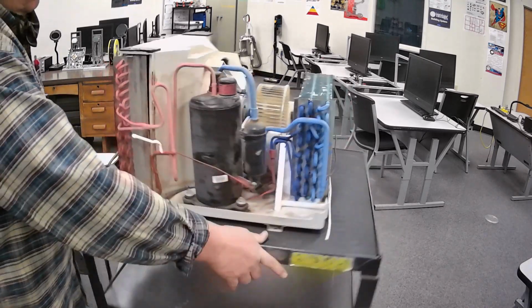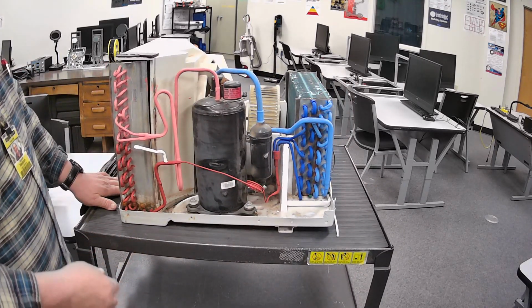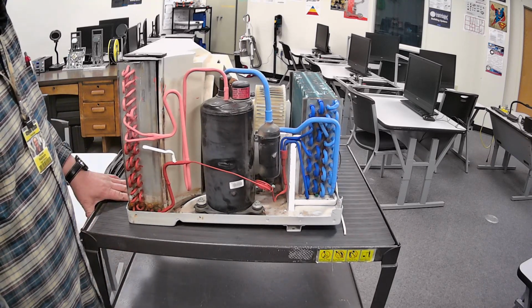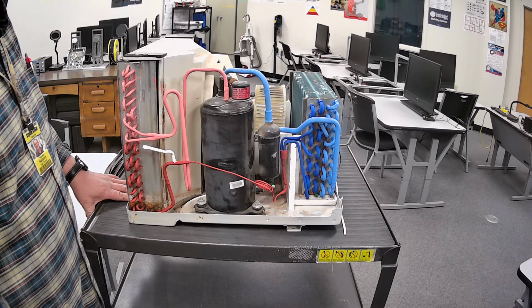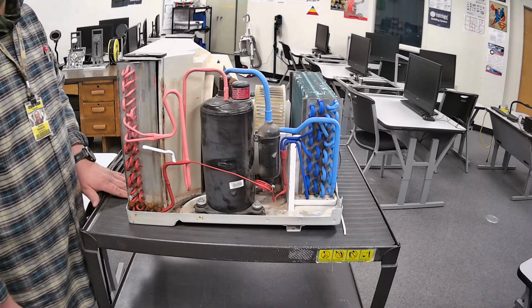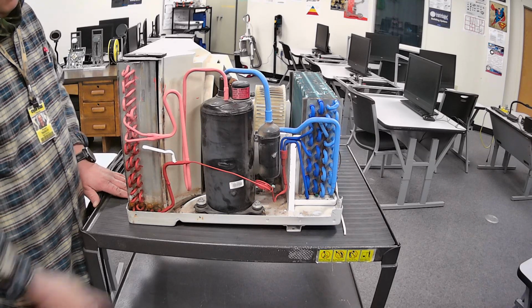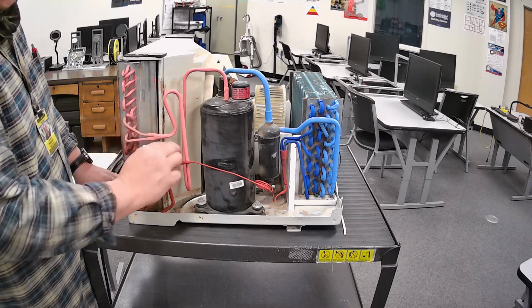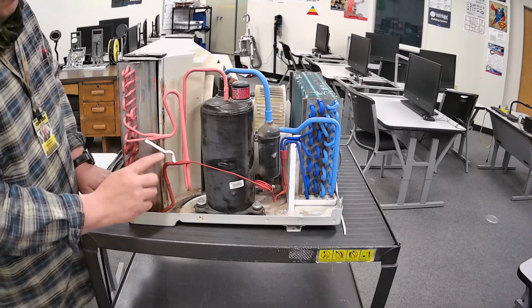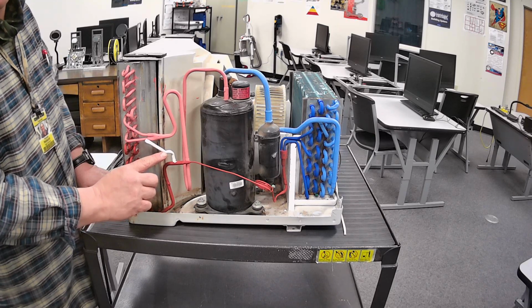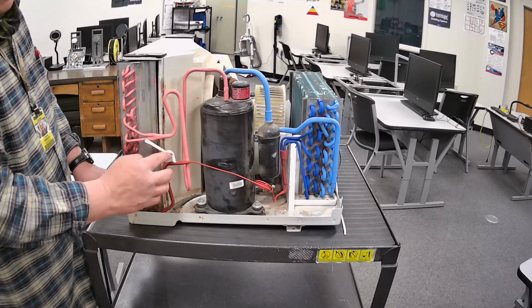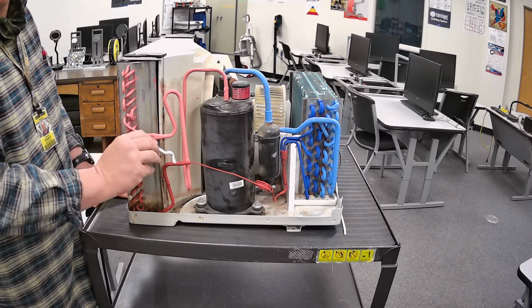Also, on a window unit, because they don't provide a service valve, they have to provide what they call an aperture, which is basically a process tube. Process stub. This is the process stub. I painted it white so you can see it, but it's basically just copper, and it's usually straight, but it's been bent. If you notice right here, there's a little pinch in it. That's where the factory charged the system and then pinched it off to keep the refrigerant from leaking, and then they brazed the tip of it so it wouldn't leak the refrigerant out.